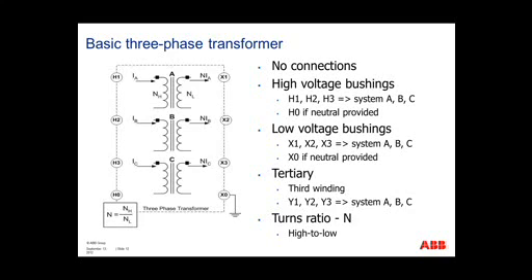Now this is just to get across the standard ANSI connections of a transformer. This is an unconnected transformer, but with the connections on the outside of the transformer, you'll see H1, H2, H3, and H0, and that refers to the connections to the high side of the transformer. On the low side of the transformer, you'll have X1, X2, X3, and X0 if a neutral is used. Now, if this was a three-winding transformer, you have included a tertiary winding, which would be Y1, Y2, and Y3. So H would be high voltage, X low voltage, Y tertiary.